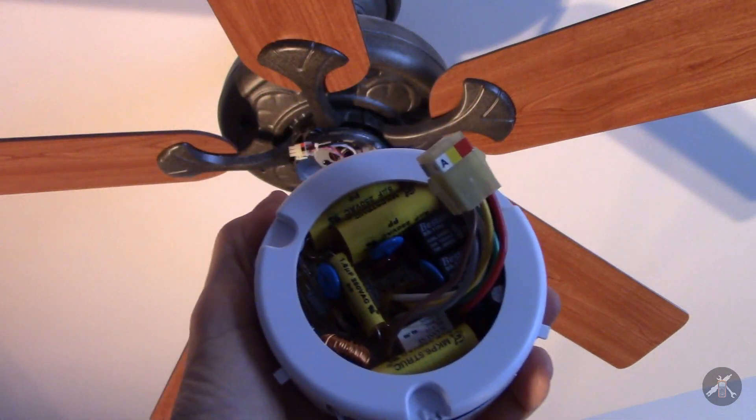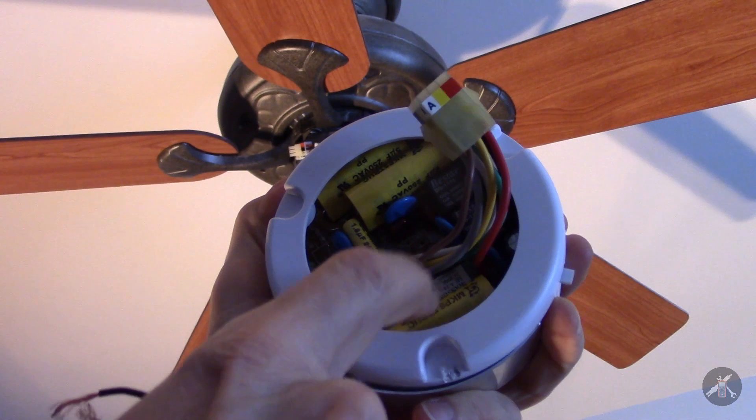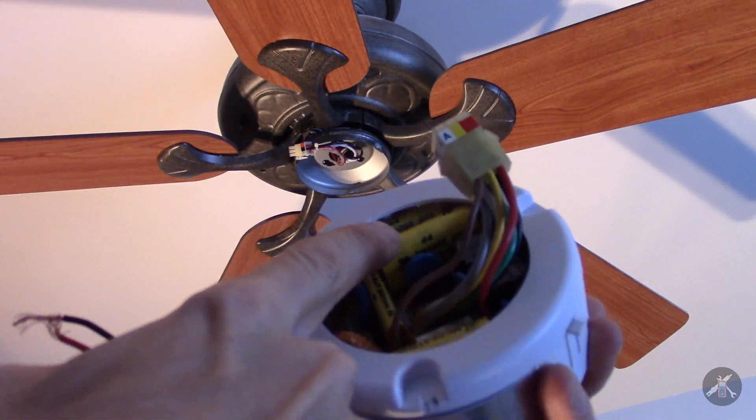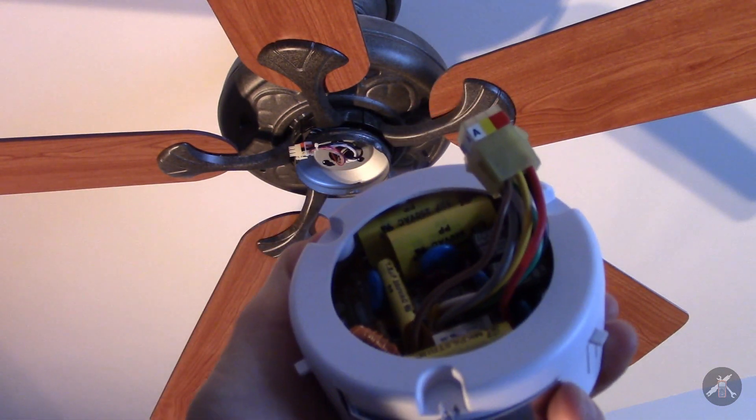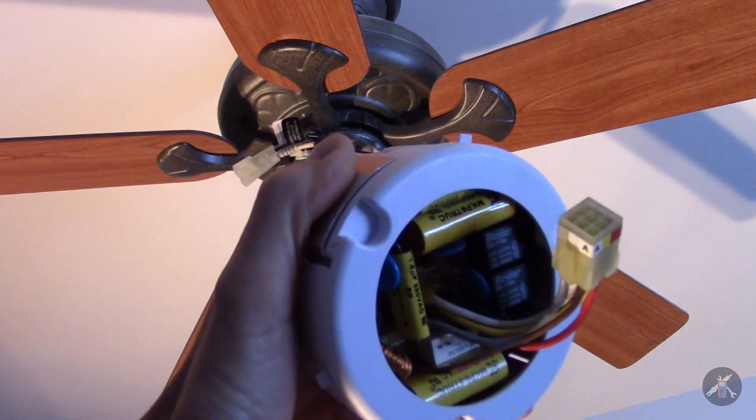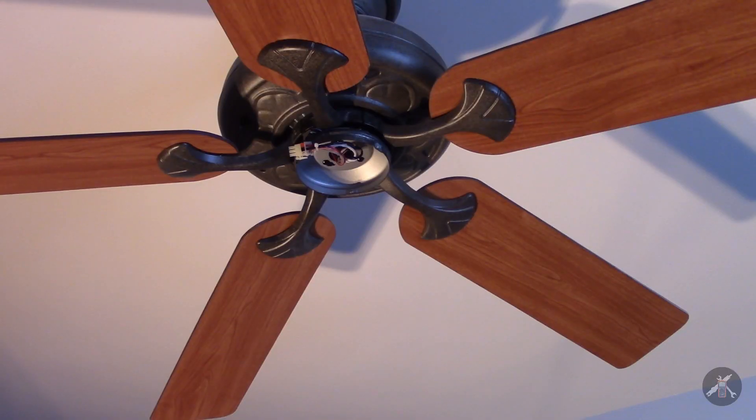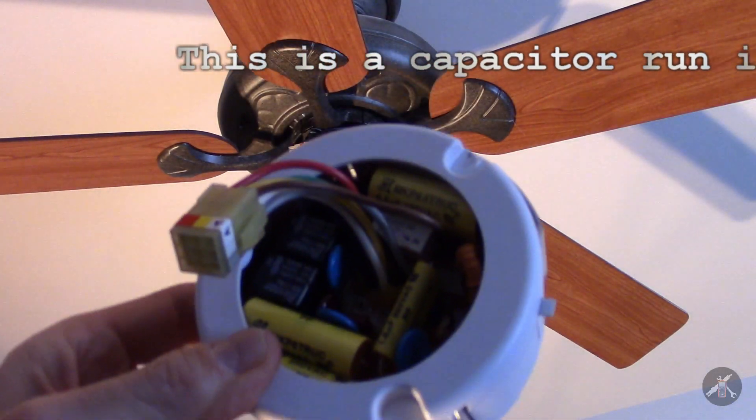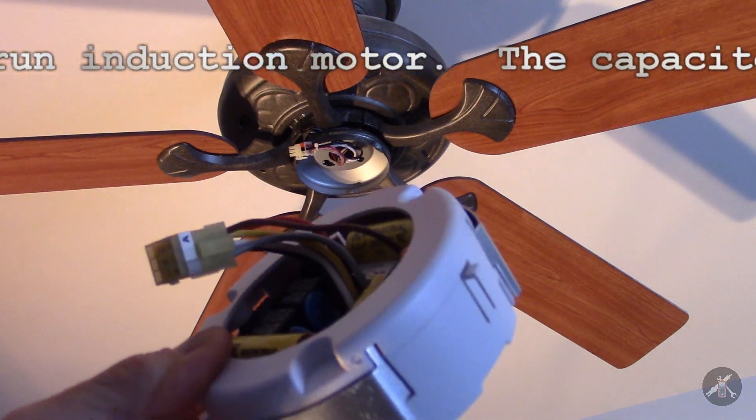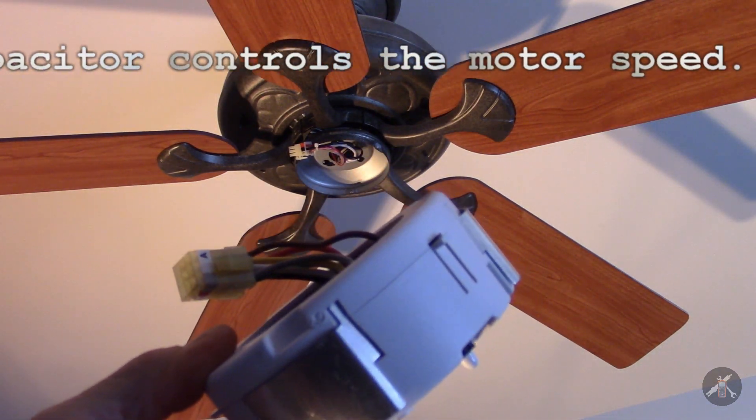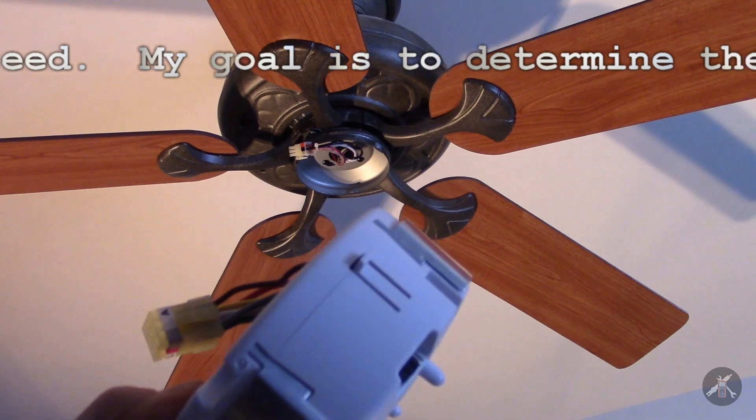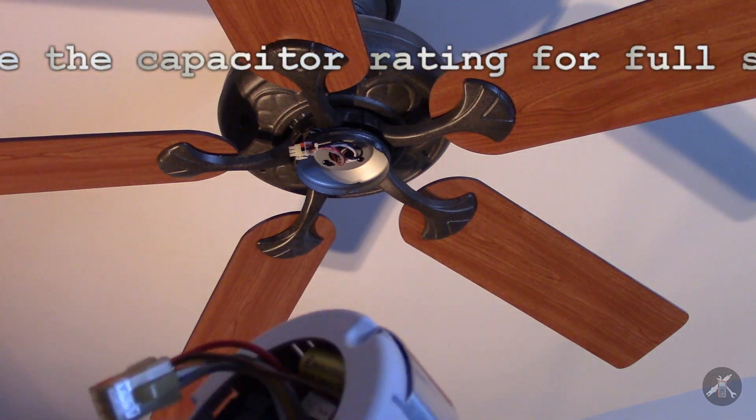I've gone through this box and there's a 6.5, a 6, and a 5 microfarad. Those are the big capacitors in the module. I can tell that the 6.5 appears to be wired between the white wire, the neutral, and the red wire for the motor winding.